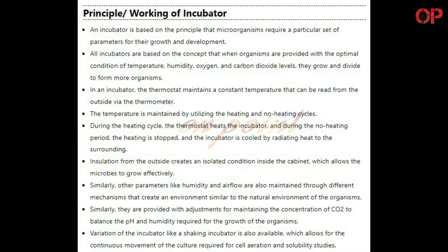During the heating cycle, the thermostat heats the incubator, and during the no-heating period, the heating is stopped and the incubator is cooled by radiating heat to the surrounding. Insulation from the outside creates an isolated condition inside the cabinet, which allows the microbes to grow effectively. Similarly, other parameters like humidity and air flow are also maintained through different mechanisms that create an environment similar to the natural environment of the organisms.